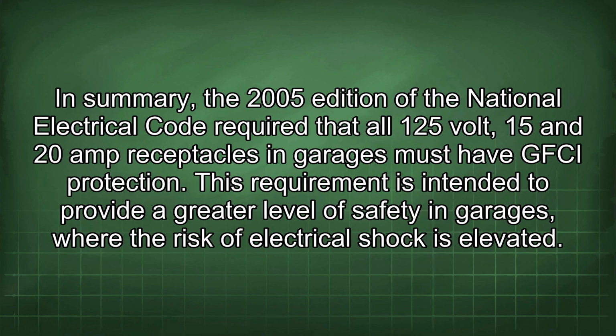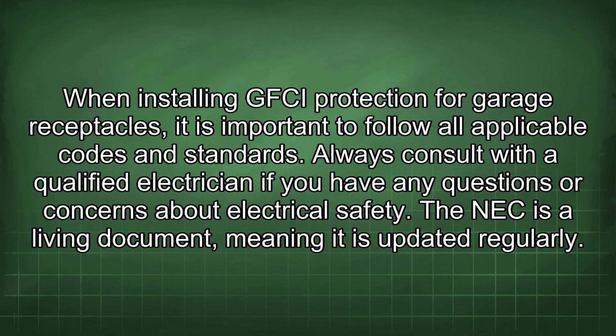In summary, the 2005 edition of the National Electrical Code required that all 125-volt, 15 and 20 amp receptacles in garages must have GFCI protection. This requirement is intended to provide a greater level of safety in garages where the risk of electrical shock is elevated. When installing GFCI protection for garage receptacles, it's important to follow all applicable codes and standards. Always consult with a qualified electrician if you have any questions or concerns about electrical safety.